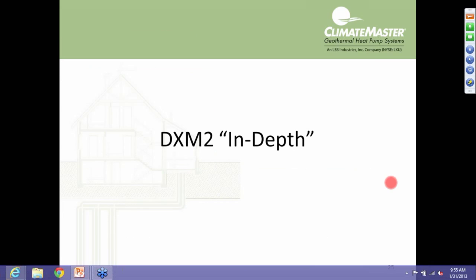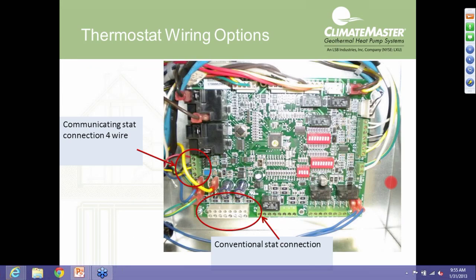All right, let's get a little deeper now into the DXM2 and then into some of our VFlow options. First, I want to talk about some of our connection points on the DXM2 control board. If you're using a communicating thermostat, you can see over here to the left-hand side where we would make our connection from our ATC thermostat. Down here on the bottom side of the control board is where we can hook up a conventional thermostat. So if we wanted to use a Honeywell or whatever brand thermostat, we'd have that option to wire in right there.